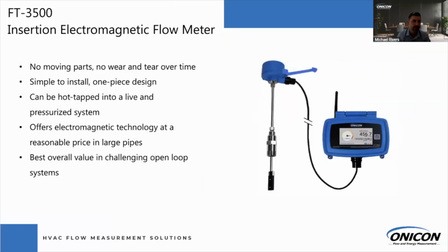Why do we like insertion mag meters so much? Well, first off, there are no moving parts. If you think back to when ONICON started in the 80s, we only had the turbine flow meter, and it worked great for clean closed loop applications. But what if the water quality wasn't as clean, for a cooling tower application, for example? That's when, about 20 years ago, we designed the insertion mag meter.